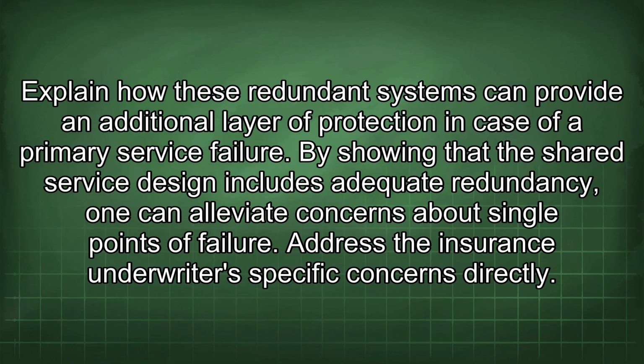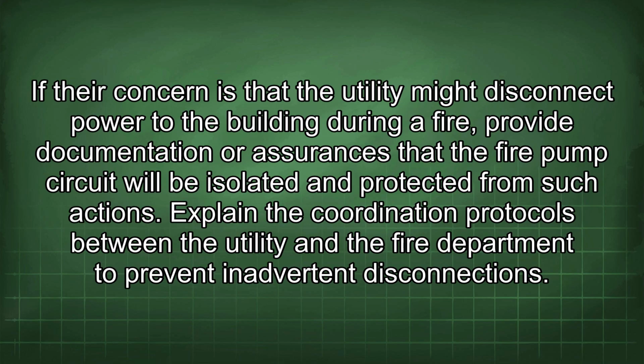Address the insurance underwriter's specific concerns directly. If their concern is that the utility might disconnect power to the building during a fire, provide documentation or assurances that the fire pump circuit will be isolated and protected from such actions. Explain the coordination protocols between the utility and the fire department to prevent inadvertent disconnections.